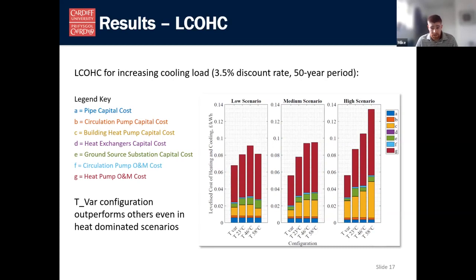Here we have the results for the levelized costs of heating and cooling. The maroon coloured bars are for heat pump and chiller operation, which is the biggest driver of costs. The capital costs for these are also significant, which is the yellow bars. The main point here is that the configurations with active cooling all perform worse in every scenario, and that the higher the temperature, the least robust it is against future increased cooling. We also see that not only does the T-var scenario demonstrate the most cost-effective option in heat-dominated scenarios, it also becomes more cost-effective as we keep adding the cooling loads. And just also to note that the pumping costs, though not a huge factor, which is F, the light blue bars, were the smallest for the T58 configuration, so less on hydraulic pumping.